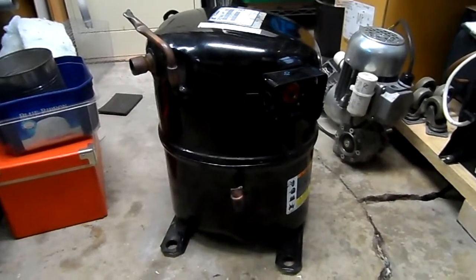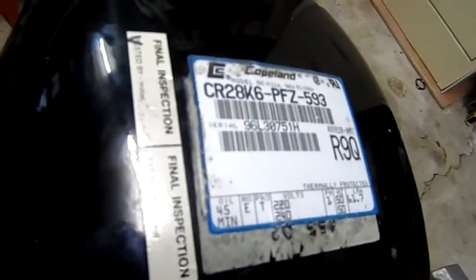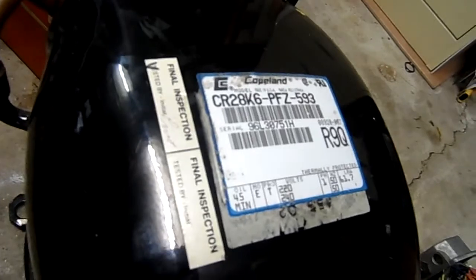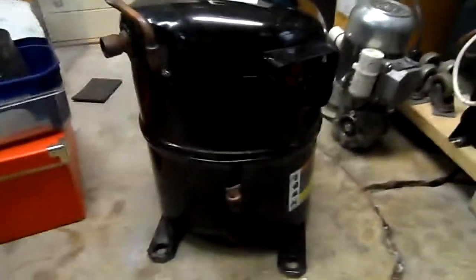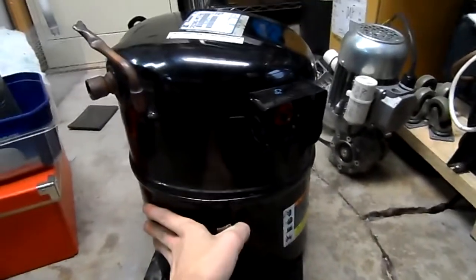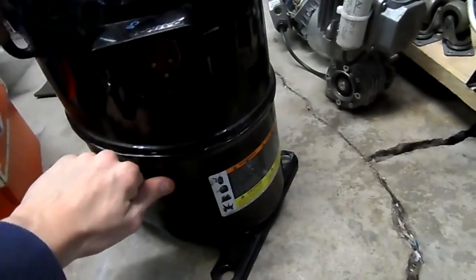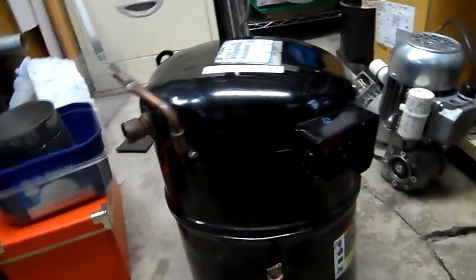G'day everybody. For today's compressor autopsy we've got this Copeland CR28K6-PFZ-593 single-phase 220-240 volt air conditioning compressor. I wasn't actually on the job that we removed this one, but it came out of a TempoZone air conditioner for a hotel room. Not 100% sure on why it failed, although the readings were quite out when I tested it. But anyway, we're going to pull it to bits and find out why it failed.